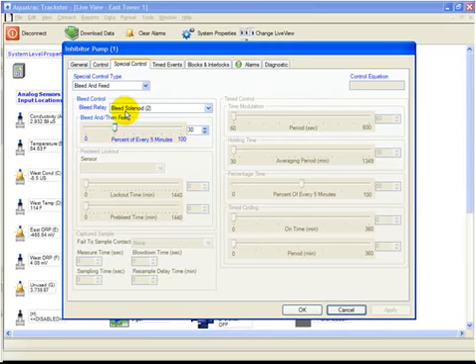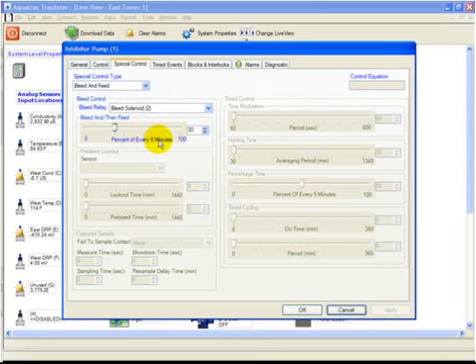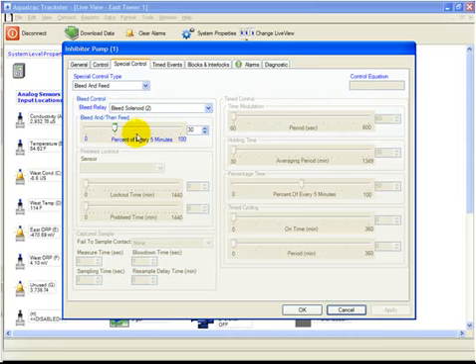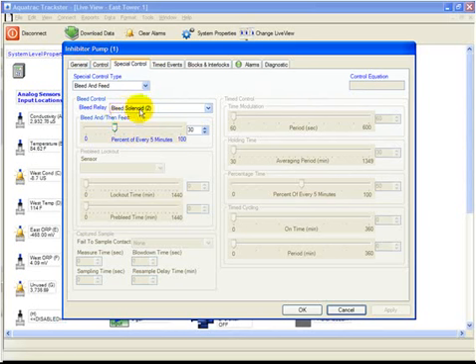If the bleed solenoid is still on in the next five minutes, it'll turn on for another 30% of those next five minutes, and so on and so forth. It's important to note that no matter what the circumstance is, the inhibitor pump will turn off when the bleed solenoid turns off. In other words, the inhibitor pump is interlocked with the bleed solenoid.